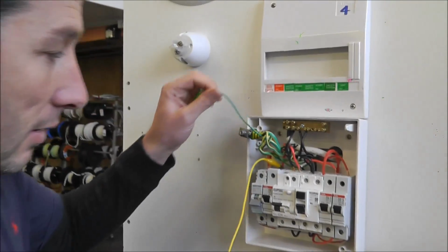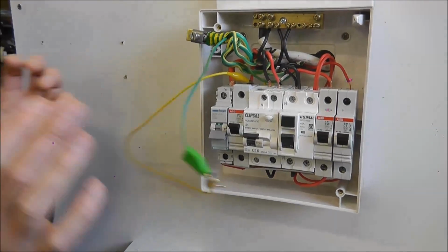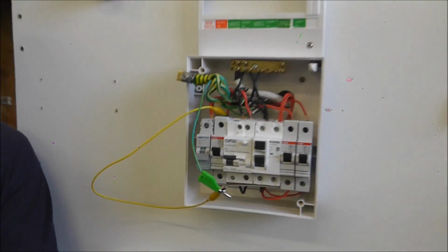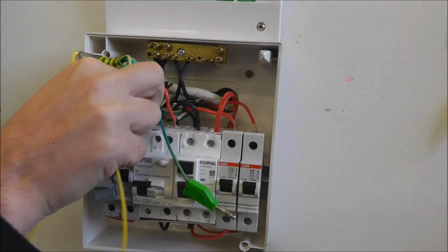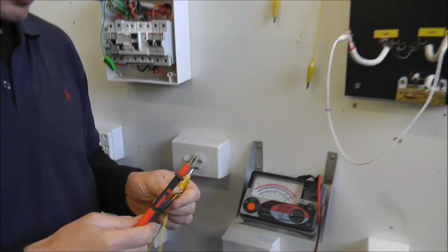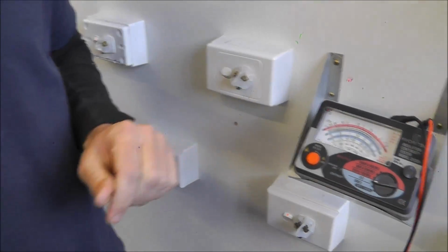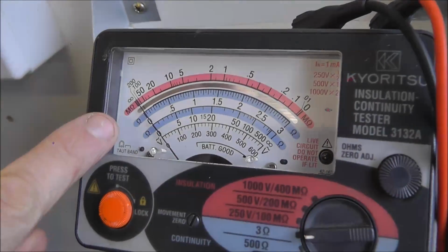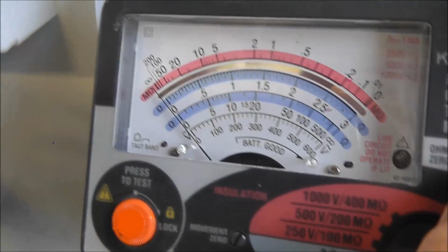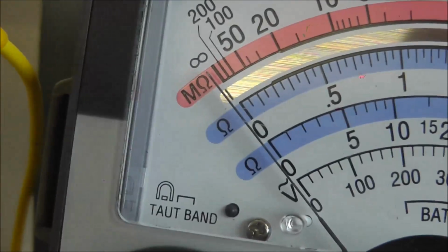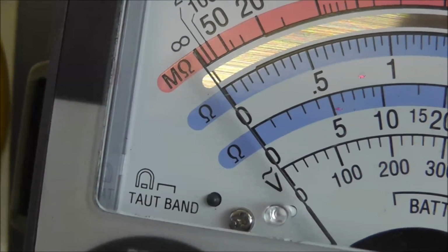But that's background. Here, I'm going to join up the active and the neutral, active and the earth. Now, have I forgot to do anything at this point? I've just caught myself. Thank you. I'm testing the active earth loop. So therefore, I need to make sure that the resistance of this lead is taken out of the equation. Now you see, Dobbo, how we're not quite at zero anymore? So I better just change that. And what I'm doing is I'm zeroing out the leads.